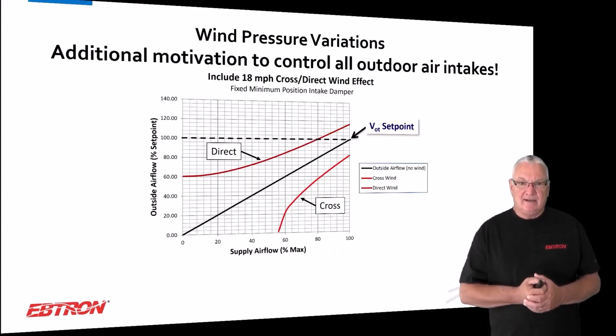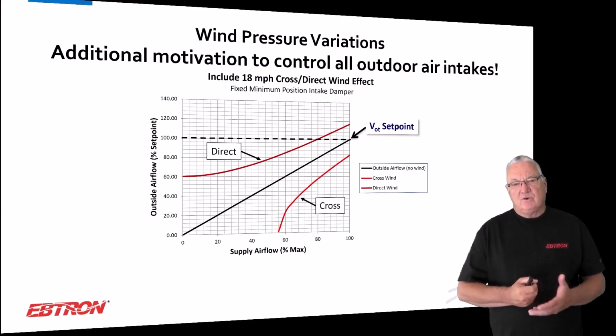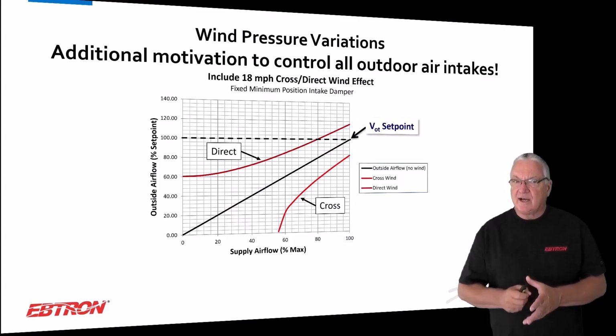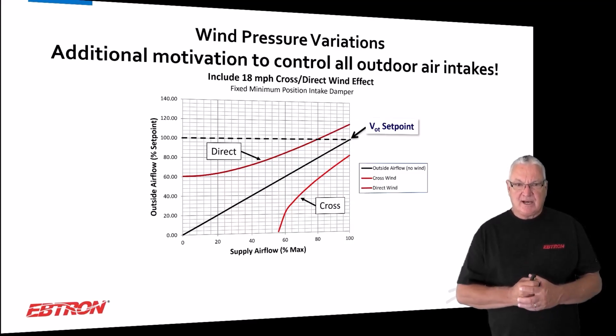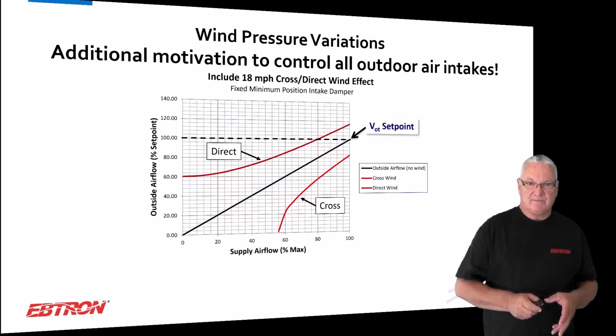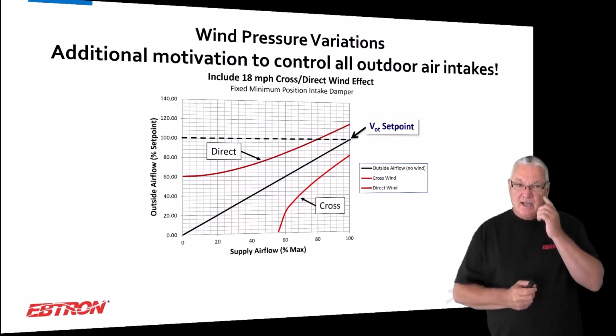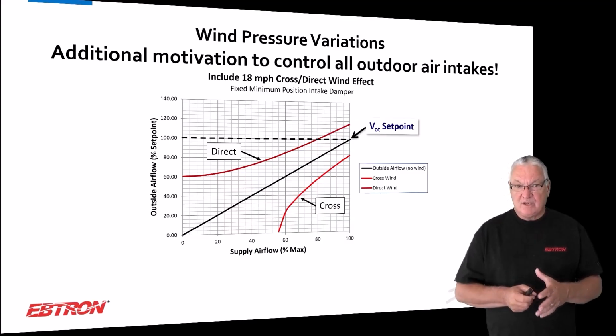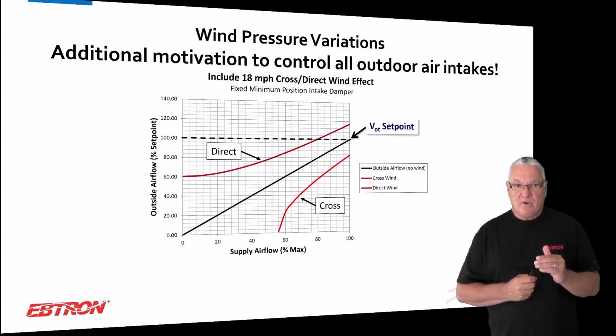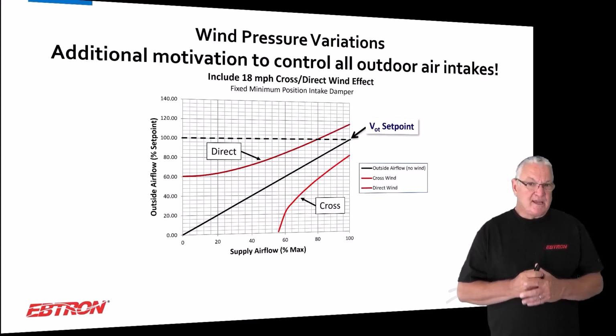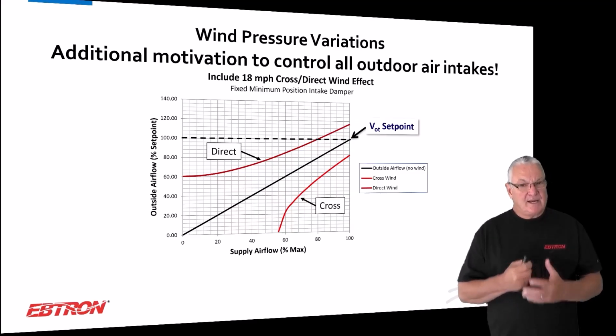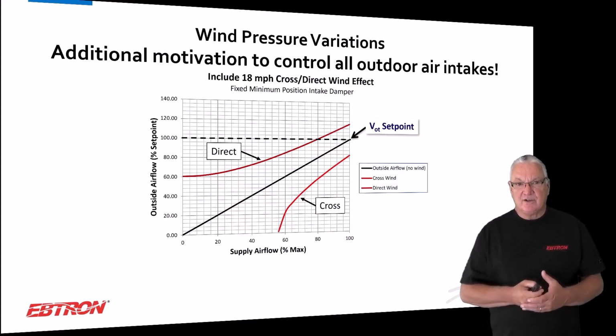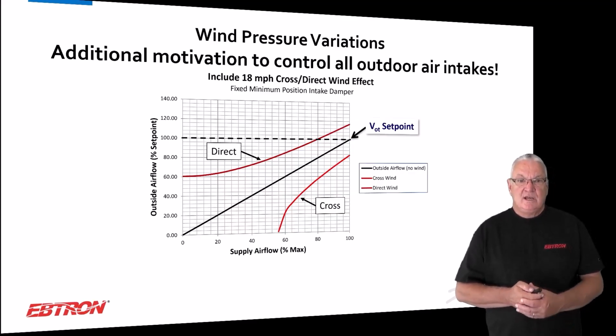Okay, and when you plot it, you look at the supply airflow, you go all the way to the right here and you look at 100%, full fan speed, that's where the 40% is going on. But now as you reduce the supply airflow, you kind of compound it, you have now the changes in the mixing box plenum pressure, plus the changes in the outdoor pressures. And so you end up with outdoor air that's between those two red curves. And look at your set point, what I showed there as that dashed black line at 100%. So in some cases you're going to be over ventilating, but in a lot of cases you're going to be under ventilating. And you can even turn your intake into an exhaust, really. And so that's wind pressure.